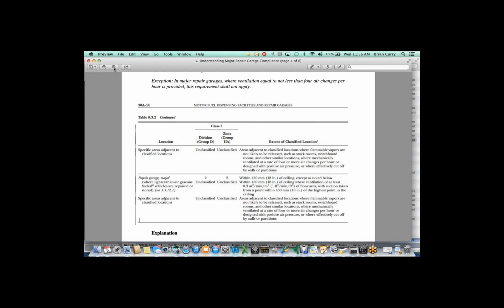As long as the shop had an open truss roof, which, I've worked with shops that were either open truss or barrel style roofs where there's rafters that were open, and looking at the common sense approach where the airflow, if I'm putting in exhaust fans evenly across the ceiling, turning that exhaust on and bringing in fresh air, there's an immediate evacuation of the entire shop air content, and it's pretty quick.